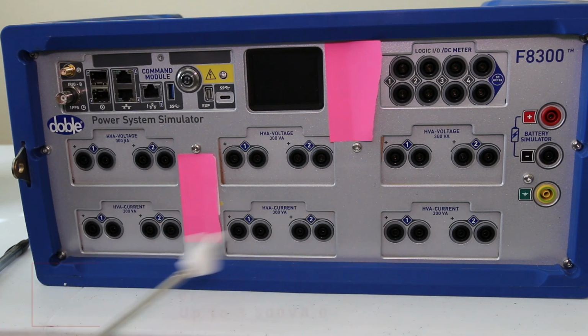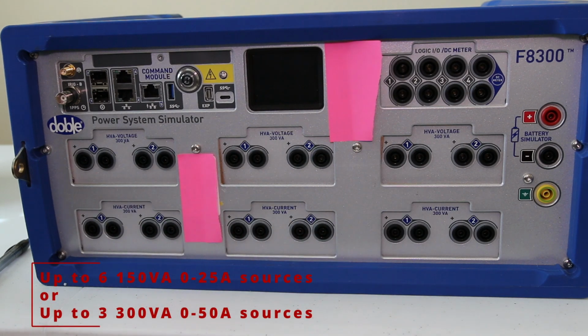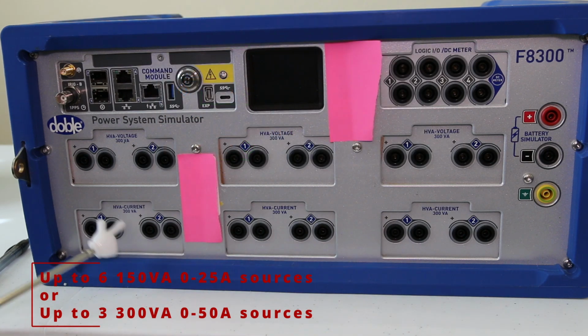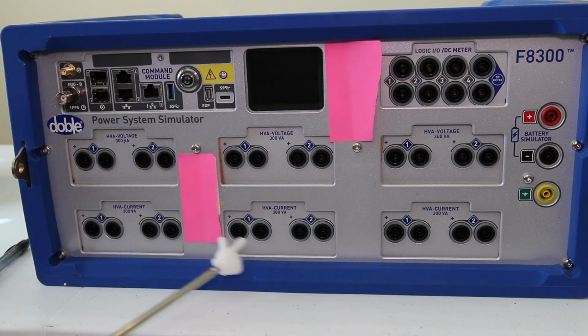The current modules are a moderate improvement over the 6150, in addition to being modular. Out of each current module, I can get two 25 amp, 150 VA continuous rated outputs, or combine them for 50 amp at 300 VA continuous, which is pretty sweet. So the way this is currently hooked up, I can either get 6 25 amp 150 VA outputs, or 3 50 amp 300 VA outputs.